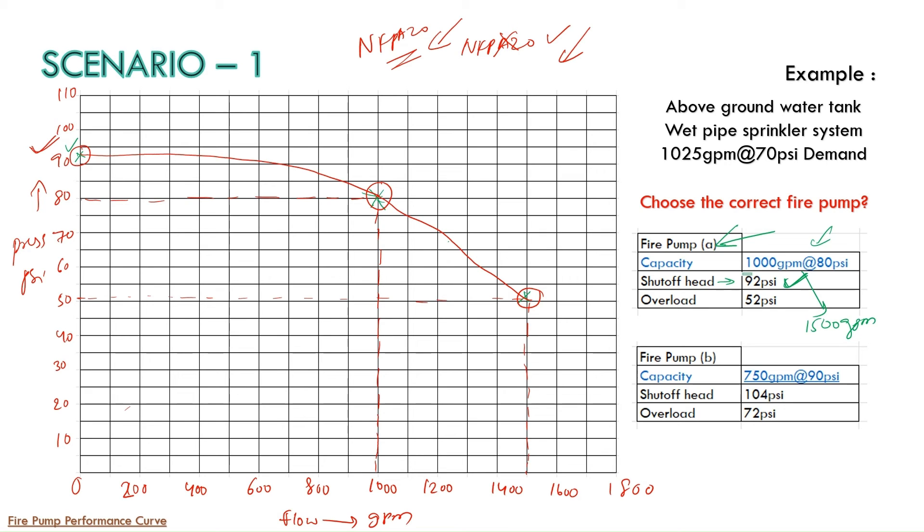So on y-axis at zero flow we consider the 92 PSI. Now we need to check our requirement. So here we have the system demand as 1025 at 70 PSI. So just we will try to locate this point on the graph. So now just we need to take the system demand and mark on the performance curve. So if you see 1025 GPM will be somewhere here and 70 PSI is here. So just I will mark this particular point in our drawing. So we can mark the intersection point. So 1025 GPM here we have and it will go till 70 PSI. So it will be somewhere here. So this is the most important and critical point you need to know.